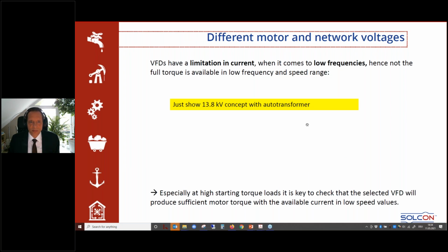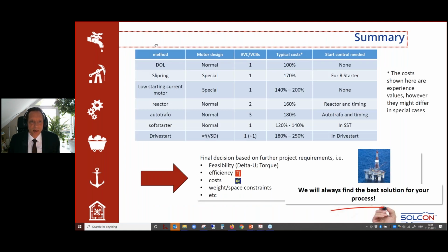So what you see here are the various methods of what I have said before: direct online, slip ring, low starting current motor, reactor, auto transformer, soft starter and drive start. And you have here a typical cost comparison. This is subjective, based on what I have experienced in some cases. You might have special cases where this differs. There is not, let's say, the method to start electric motors, and you might have different requirements.